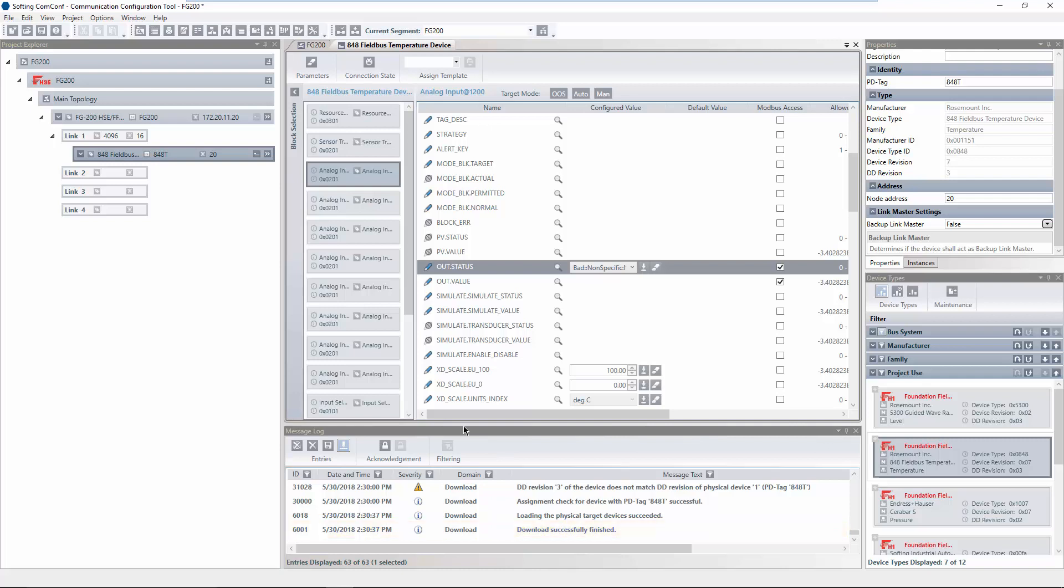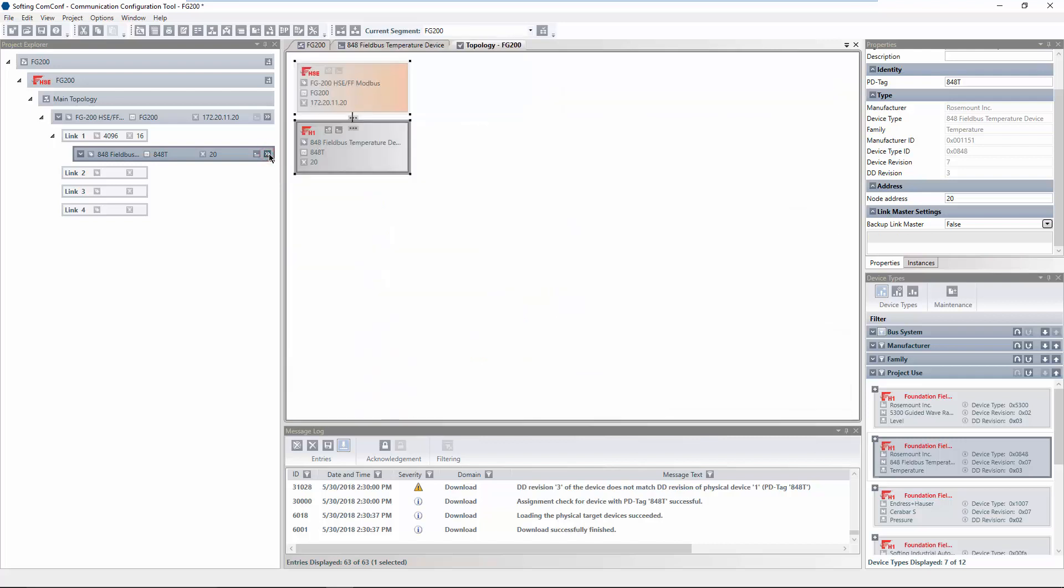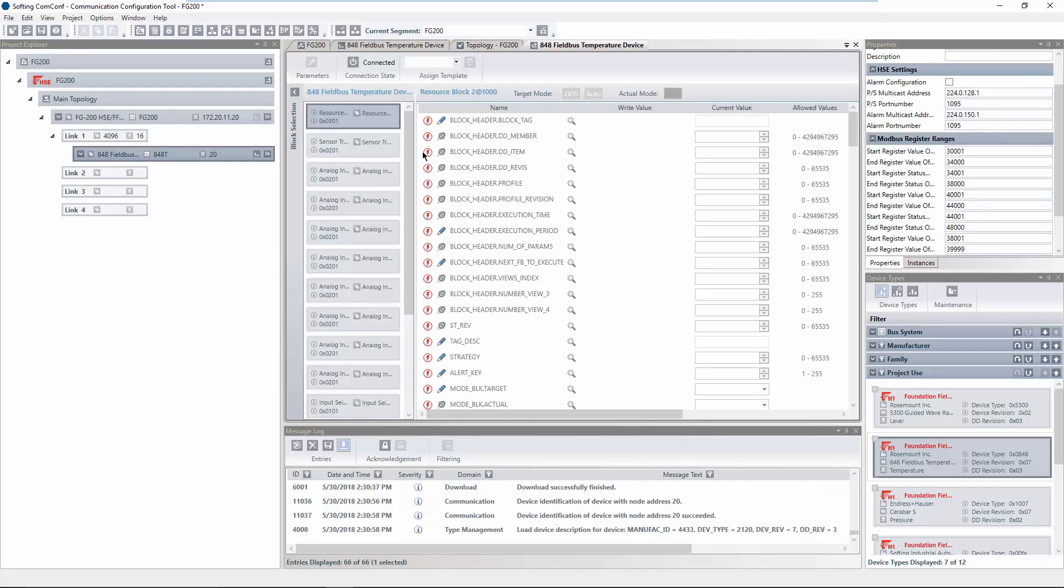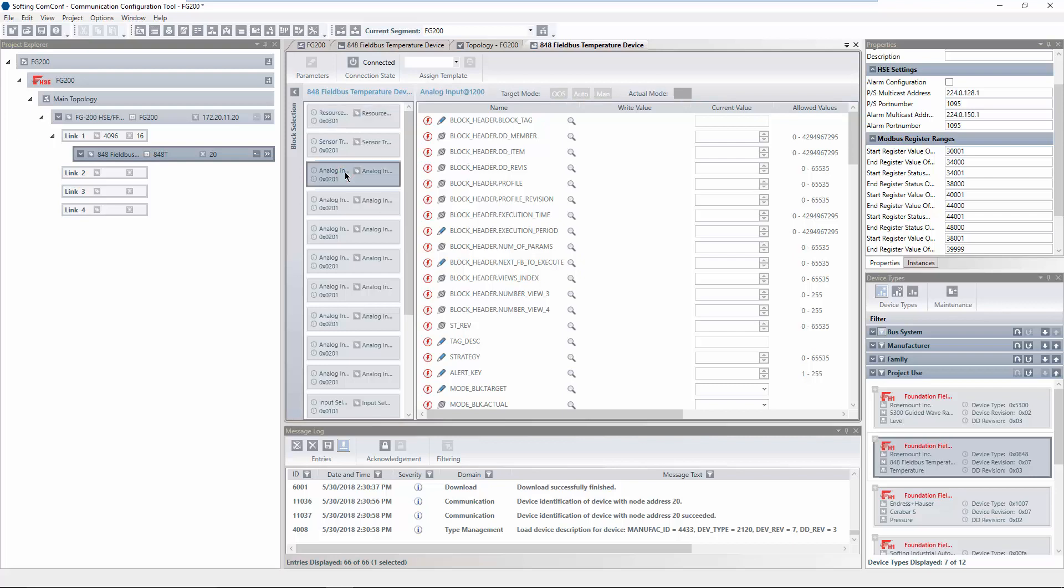In the following, we will have a look at the current process value of the previously configured block. Click on Show in Topology View of the FFH1 device. Click on Edit Device Parameters of the FFH1 device and select the corresponding block. Wait until the parameter values are read. You can identify this via the green checkmark. Verify that the actual mode is set to Auto.